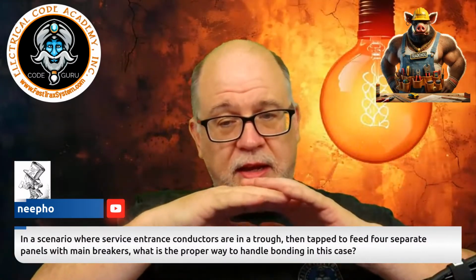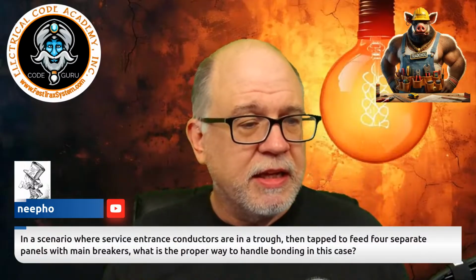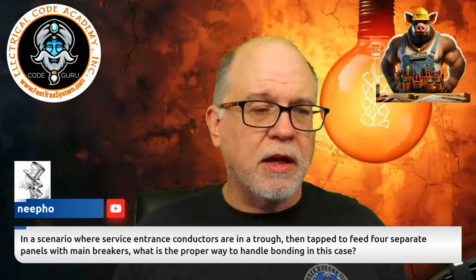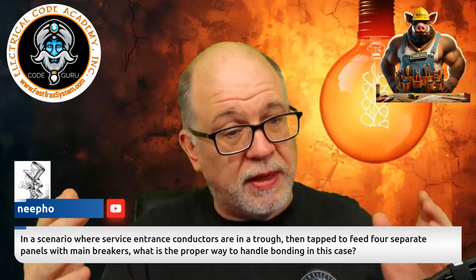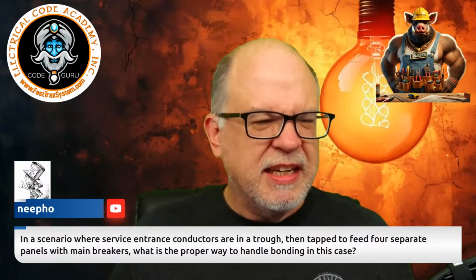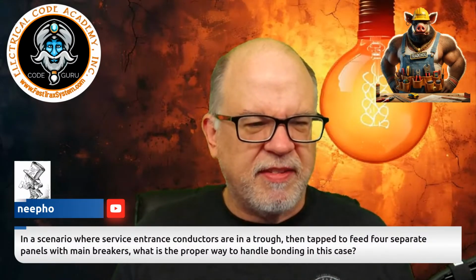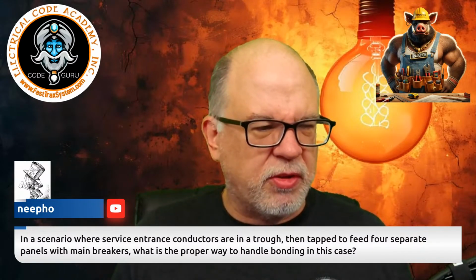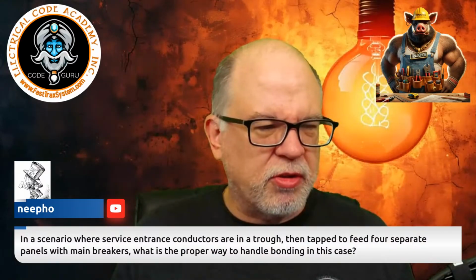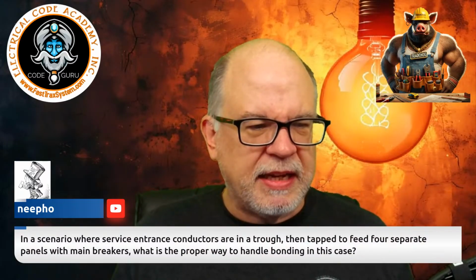230.70A1 and A2, and 230.72 for the grouping and all that kind of stuff in your code book. If it's coming down and it taps to 4 separate panels and main breakers, what is the proper way to handle bonding in this case?